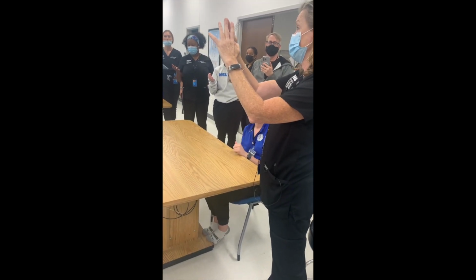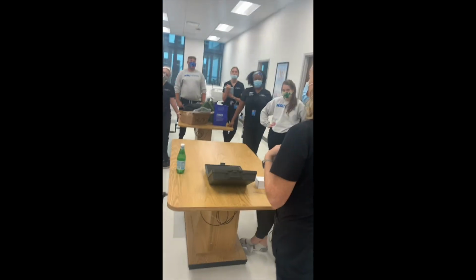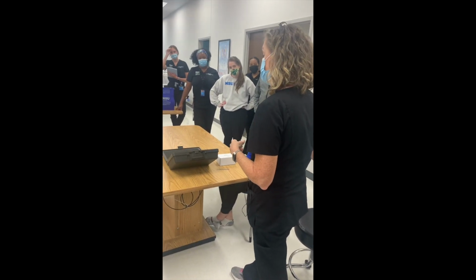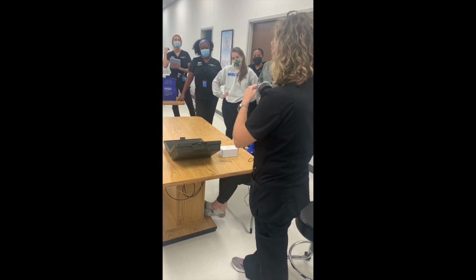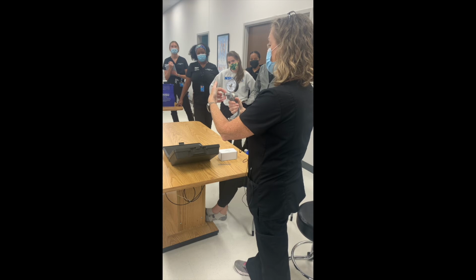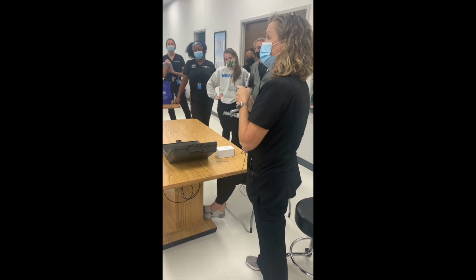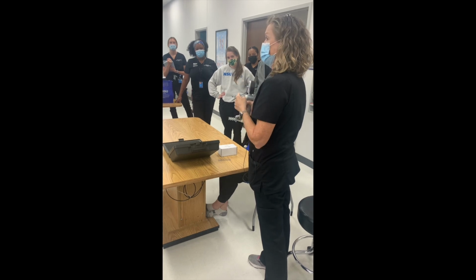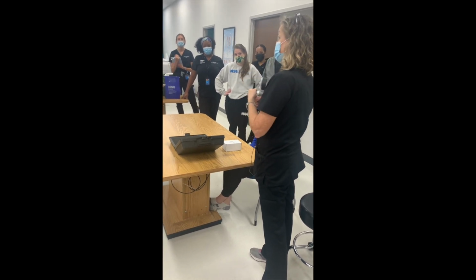On the dynamometer, there's a very specific way you're supposed to do this. All the research done on norms for grip strength is on rung number 2. You will get this back from your PT counterparts, and they do it on rung 3, so make sure you put it back on rung 2.